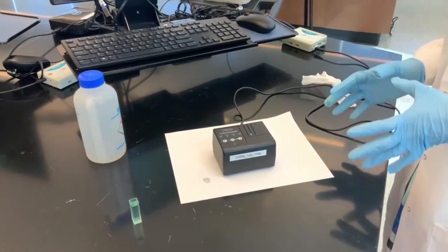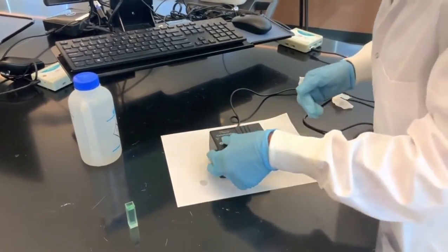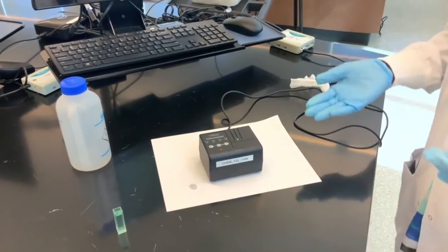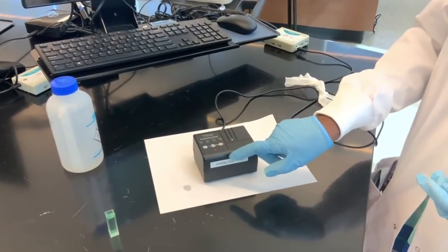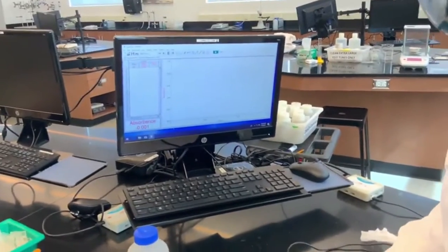Once we change the wavelength, we have to make sure we calibrate again. Anytime you change wavelength, you have to calibrate. So you hit calibrate, and it's calibrating until the red flashing light goes off.